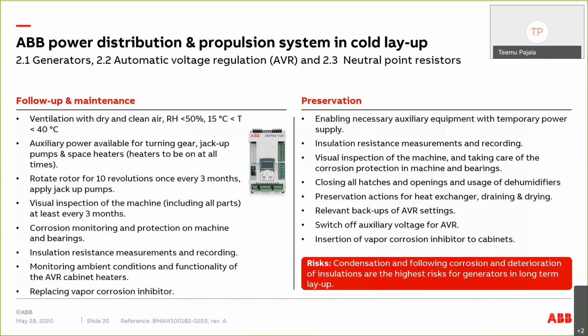And for AVR in general, it's important to keep the heaters on so that no humidity comes inside, but at the same time keep control of the temperature so that they don't get too hot. For preservation, for some equipment this temporary power supply is needed, like mentioned before. And all hatches and openings should be closed, and dehumidifiers used inside cabinets, inside the equipment, to make sure that inside there is the equipment's own atmosphere where the humidity is less than outside.